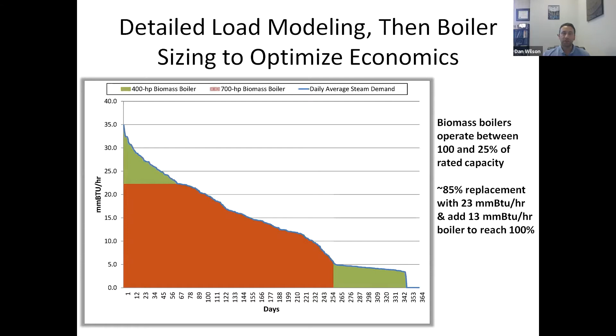One common approach to sizing a wood energy system is to select one unit that is going to cover 80 to 95% of the load. That means you're covering 80 to 95% of the load, or capturing 85 to 90% of the savings with that one unit. So that's an efficient way economically to capture savings. And then for facilities where it makes sense from an economic perspective or redundancy perspective, you can add in 2 or 3 wood boilers in total to cover 100% of the load, or provide redundancy for the systems. In most cases, not all cases, but most cases, you will have a backup fossil fuel system that covers peaks, downtime, or low loads that the biomass energy system doesn't happen to cover.